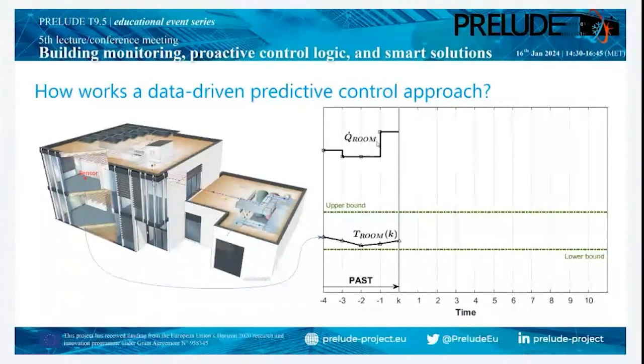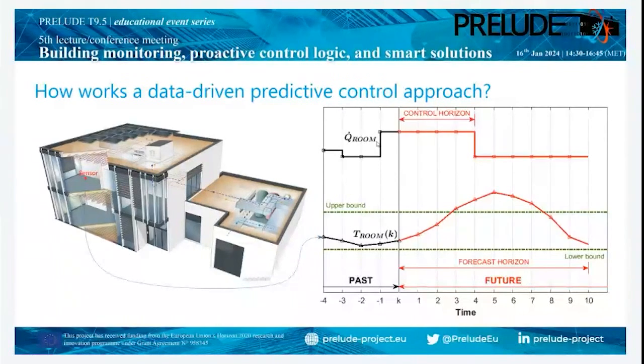With the data-driven predictive control approach, we want to build up the future behavior of the zone for a finite time horizon, and therefore the approach will consider different control variables. You see in this slide, the forecast horizon is, for example, 10 time steps, and the control horizon is only 4 time steps. If we switch on the heating power in this room for the next 4 time steps, the room air temperature will increase, and you see that with the 3rd time step, we have a violation of the upper bound of the room air temperature. So the data-driven predictive control approach doesn't have a set value of the room air temperature.